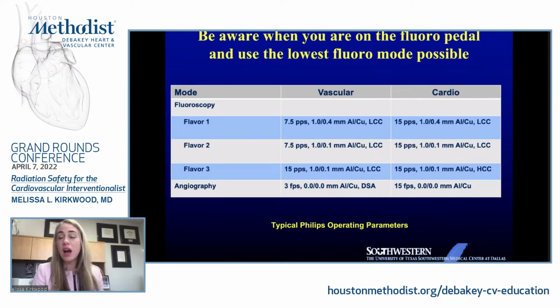Each different operating system has different flavors of fluoro. We tend to use Philips, and so they have fluoro flavor 1, 2, and 3. And as you go up in fluoro flavor, you're going up in dose. Now, sometimes it's necessary in a very large patient because increasing the fluoro flavor increases your spatial resolution and helps you see better. It degranulates the image. However, you can see that not only are the frame rates increasing, but the aluminum and copper alloy filters are being pulled, which gives you a stronger beam. So if you have to go up, make sure you go down.